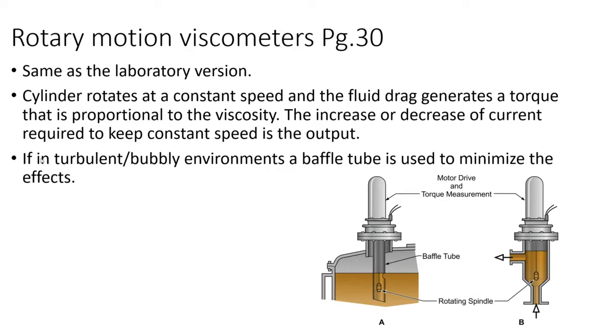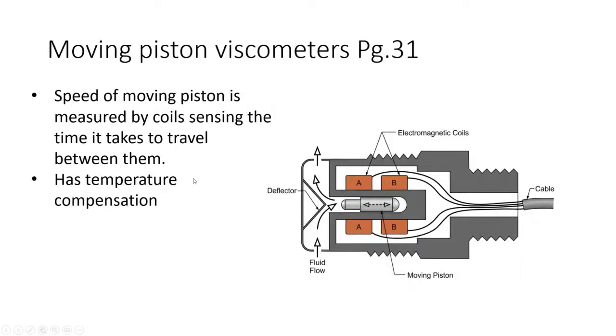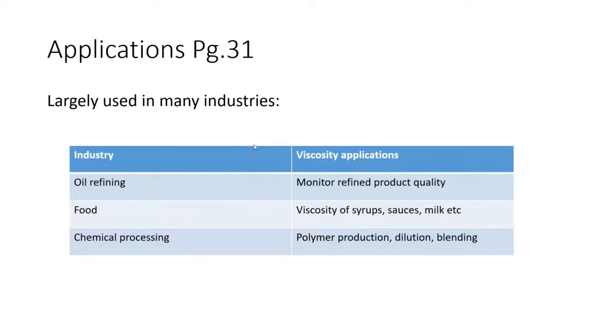The moving piston viscometer: fluid flows in and a piston moves back and forth. The speed of the moving piston is measured by coils sensing the time it takes to travel between them — similar to the ball prover in flow measurement. It has temperature compensation. If viscosity is low, the piston moves quickly; if viscosity is high, it moves slowly.